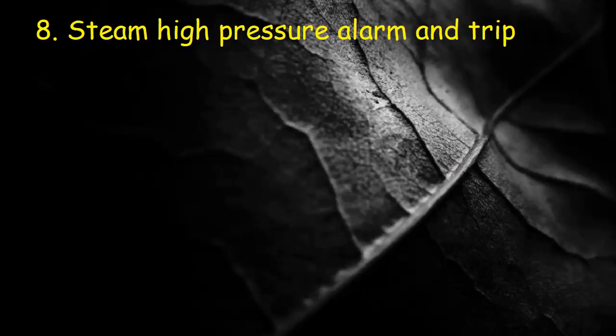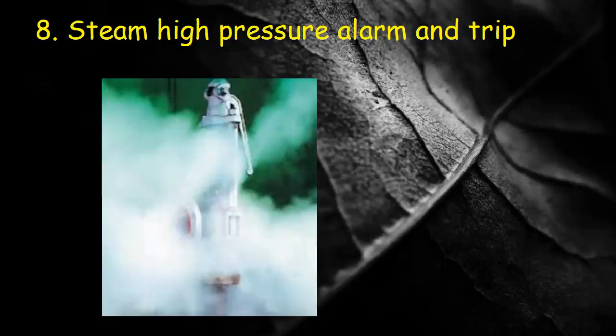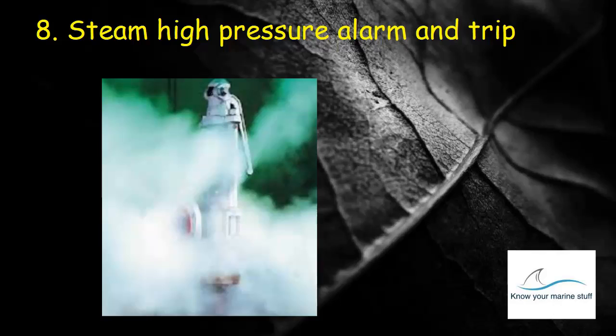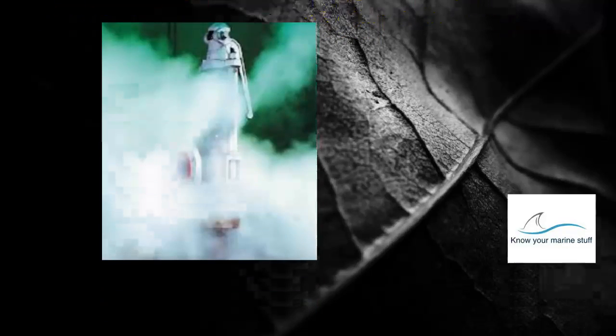Steam high pressure alarm. Steam high pressure alarm with trip to burner occurs to prevent the damage to the steam drum due to excessive pressure. The high pressure cutout will stop the burner and should never be overridden in any case.